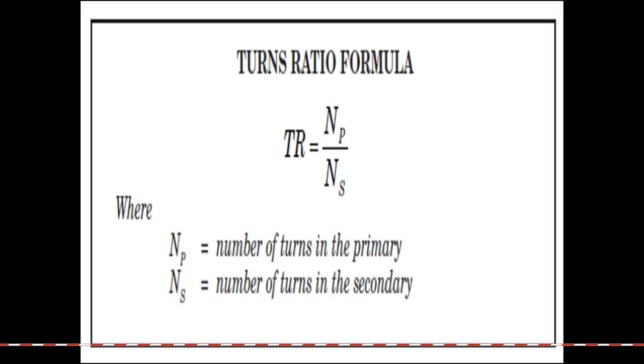These windings get coupled down really strong, which is why you hear transformers humming. When you put a positive on one side, it creates a negative on the other, and those transformer windings pull together. If you let those windings move too much, they would chafe off, and we'd short out some windings in the primary or secondary.